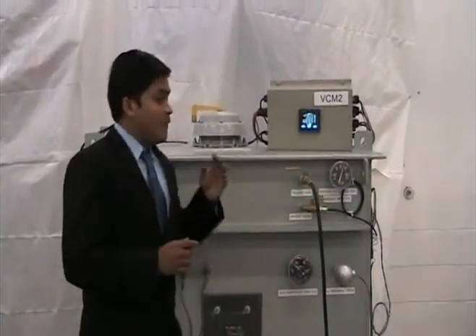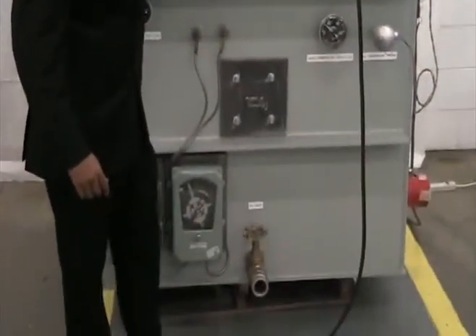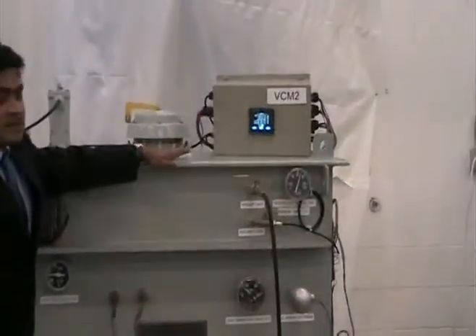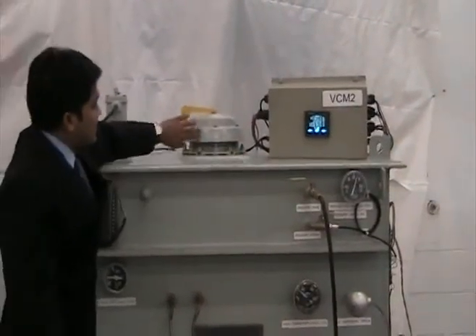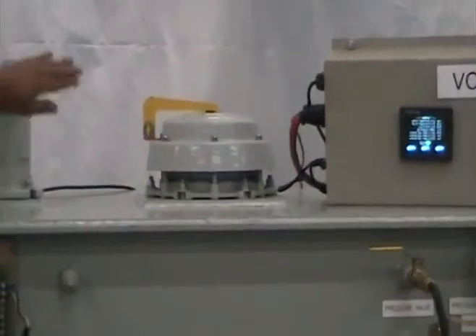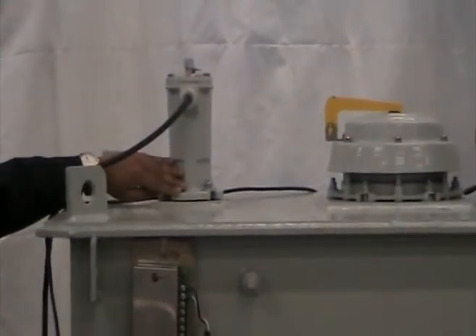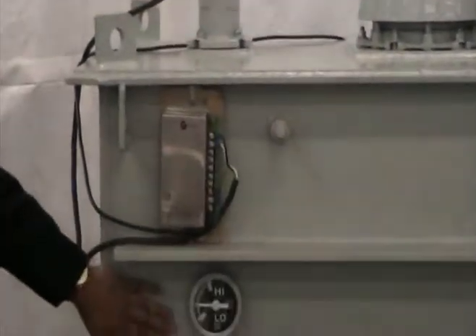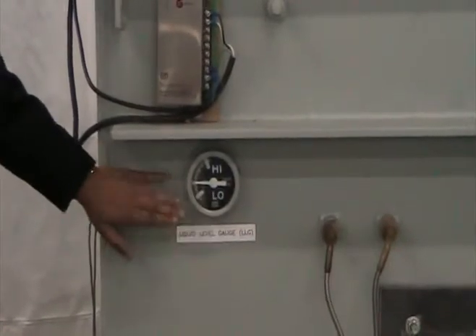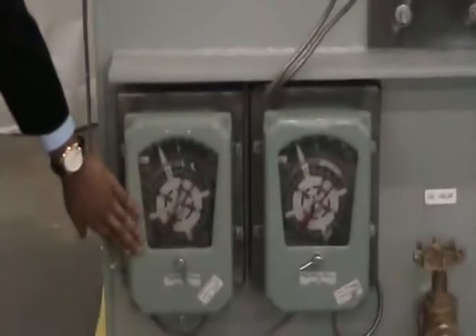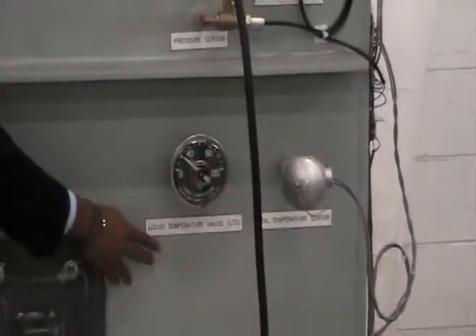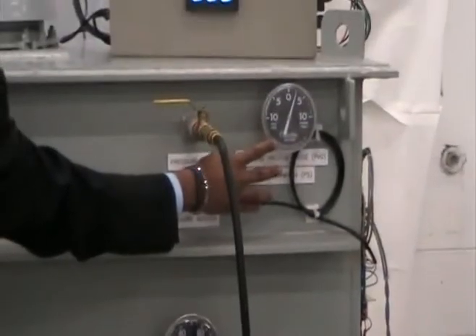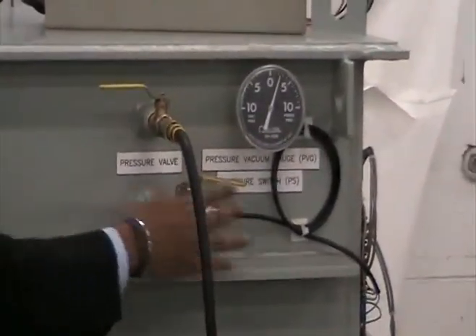Now I will show you the test setup for VCM2. For this demonstration, we have built a transformer model. On this model, we have installed various analog gauges such as pressure relief device, sudden pressure relay, liquid level gauge, winding temperature gauge, liquid temperature gauge, pressure vacuum gauge and VCM2 sensors.